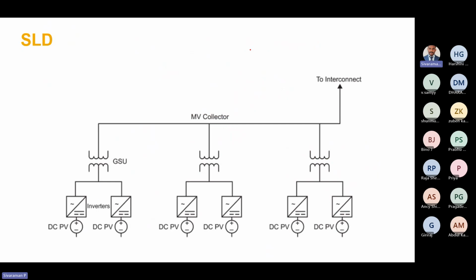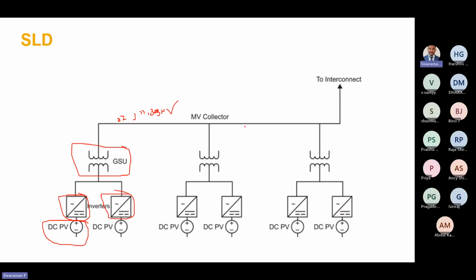Okay, so this is a simplified single line diagram. This diagram is clearer. This is a solar inverter. This is a solar PV module. The solar PV module is connected to the inverter. This is a transformer, an inverter duty transformer. Then this is the medium voltage. It can be 22 kV or 11 kV or 33 kV. Here it is 33 kV. This line is normally called the collector network. These kinds of medium voltage lines are called the collector network of the solar PV plant.